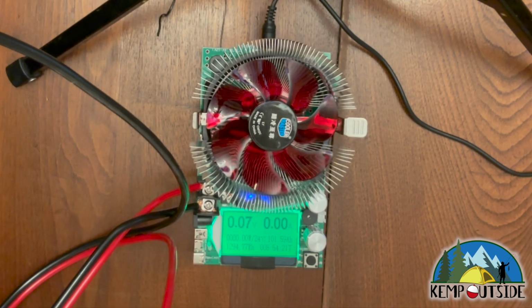All right, you can see the MakerHawk has finished its test. It's only receiving 0.07 volts, which means the BMS shut down on the battery, and it drew 101.59 amp hours out of the battery. So this 100 amp hour battery is indeed a 100 amp hour battery, and it pulled out 1,294.77 watt hours, which is exactly what it should be.